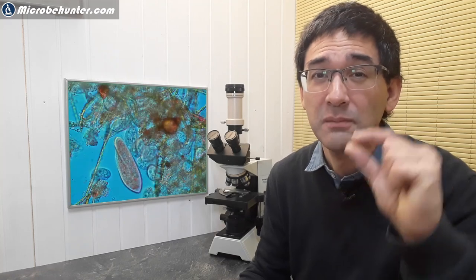If you have—I've seen some microscope cameras with nine megapixels or so—quite expensive, and I'm asking myself why would you need that. The sensor is quite small, so that means the pixel density is extremely high. This means there are other negative effects like a worse signal-to-noise ratio and worse low light performance.